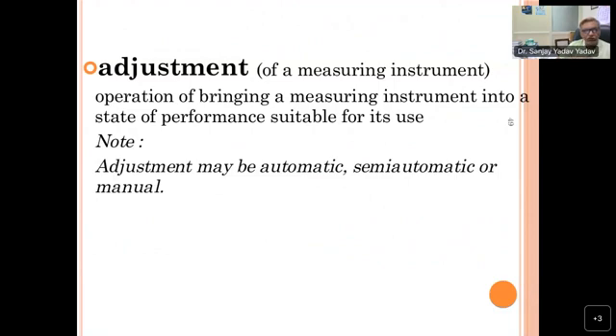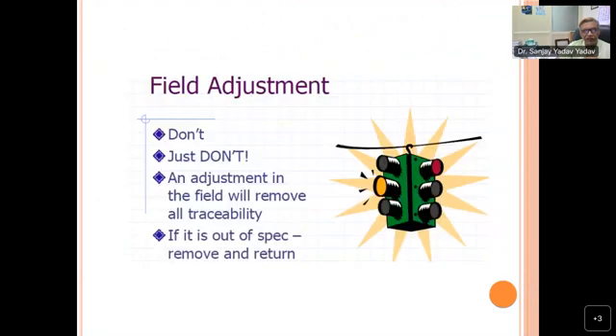Adjustment. Sometimes you have to adjust your instrument before the measurement, but there are implications in how to make that. This slide I always show on field adjustment. You try until you can apply. Don't apply. Just don't apply. An adjustment in the field removes all traceability. So that is my point of view. If it is out of specification, remove your instrument, get it calibrated, and then do the experiments again.